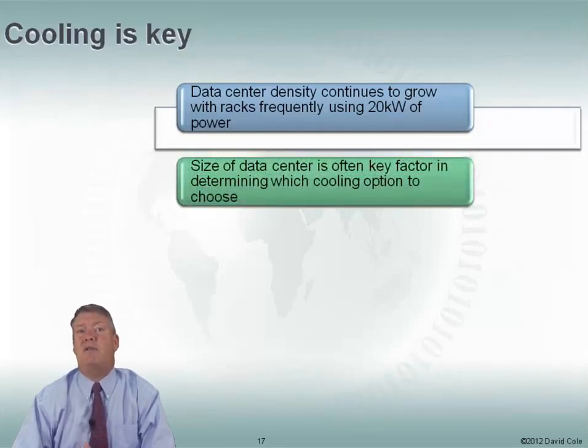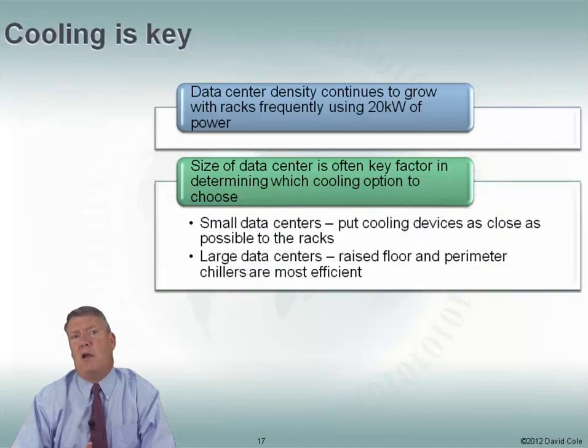Size of the data center is often a key factor when figuring out which cooling option to choose. Should I go with perimeter cooling? A large data center might use raised floor and perimeter chillers. A small data center might make more sense to put cooling devices closer to the racks, looking at in-rack cooling, in-row cooling, and so on, all the way down to individual rack cooling. So the size of the data center is a key component. We need to look at our data center up front before we design it and figure out what makes the most sense as we move forward.